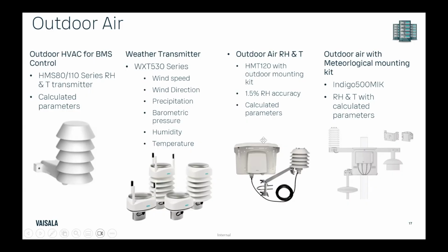So over on the right here, you will also see the HMT 120. This is the offering that includes the rain shield for the transmitter that just has a little lip over to guard from any rainfall pooling or anything like that. And then again, the radiation shield. And then over all the way on the right, we have the Indigo 500 with the meteorological mounting kit, the Indigo 500 MIK. This will be highlighted in the next few slides. But I wanted to just make note that the common theme between all of these is the radiation shield. You'll see it on each of these instruments. That's a recommendation that we will always give if you're installing any of our transmitters outdoors.